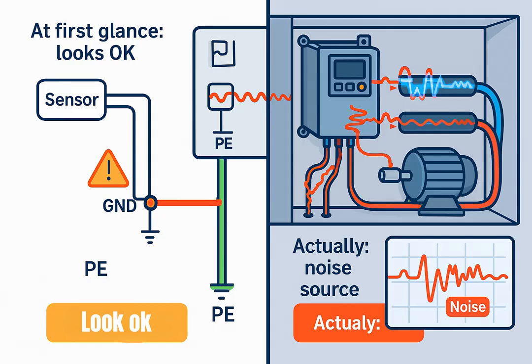Even if the sensor outputs a clean 0 to 10 volts, the PLC sees a dancing signal because the ground itself is moving. On the HMI, you'll see the value jumps, flickers, or drifts, sometimes causing false alarms. The trend graph looks like spikes and ripple instead of a smooth line. Technicians get confused, suspecting sensor failure or PLC problems. Even without a VFD, the PE bar may not sit at a perfectly stable 0 volts due to leakage currents, switching power supplies, EMI, etc. So it is not a good choice as a reference for small analog signals.